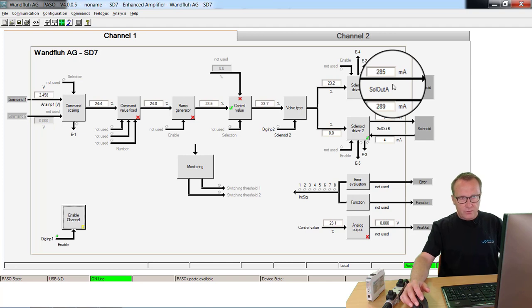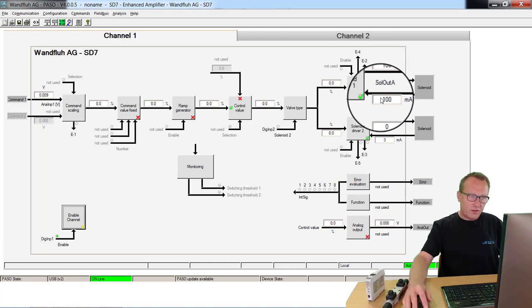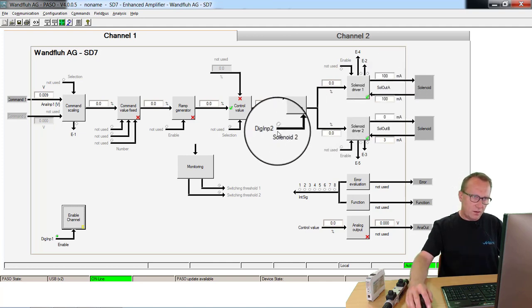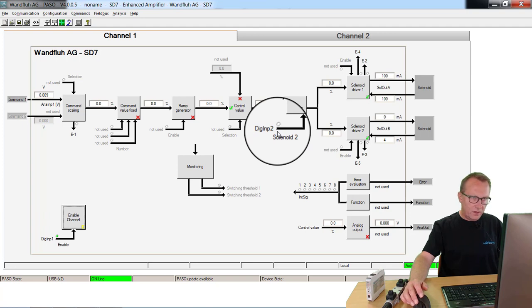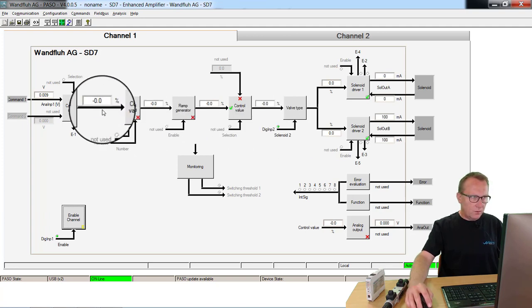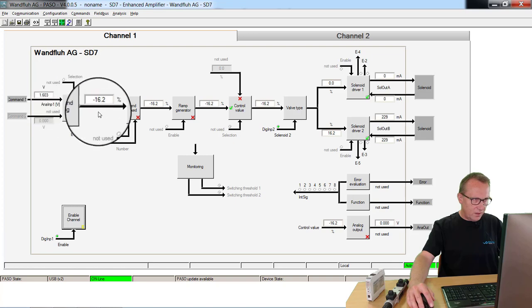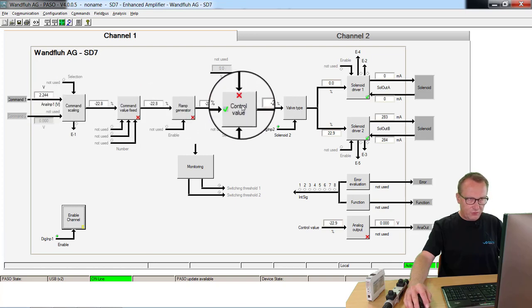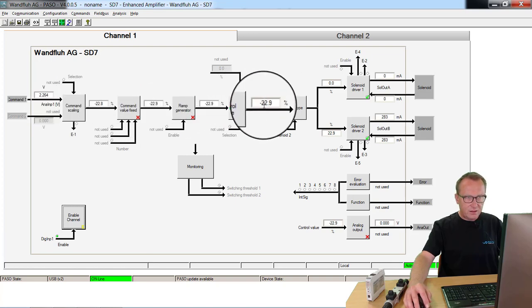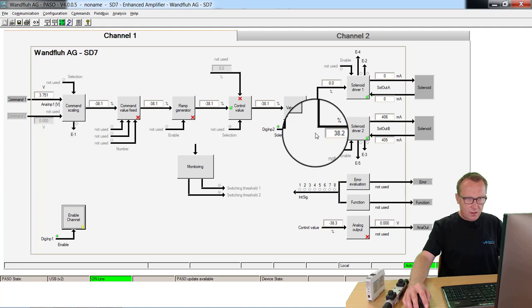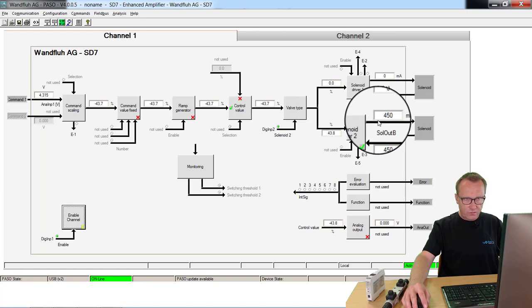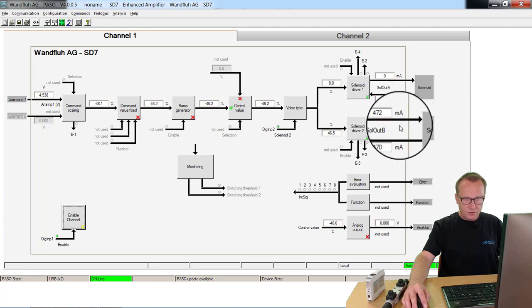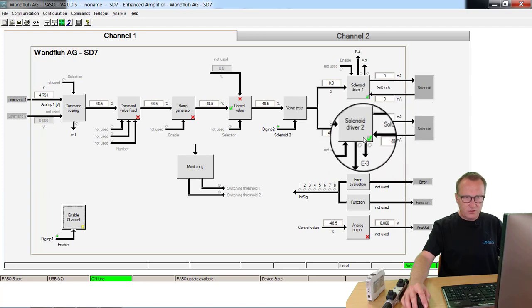If you will switch over to the other direction, you have to activate this input here, the digital input 2. Now from the same potentiometer value, internally we create a negative value. This negative value controls here and now solenoid driver 2.